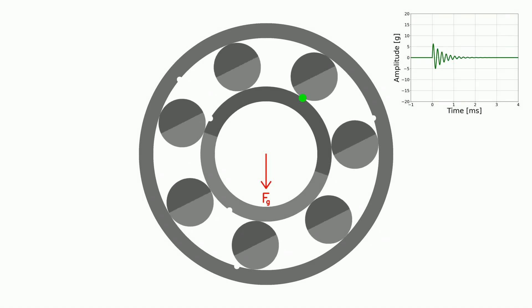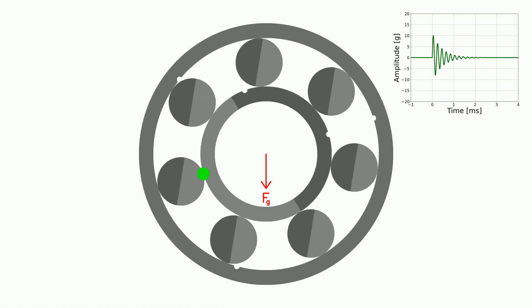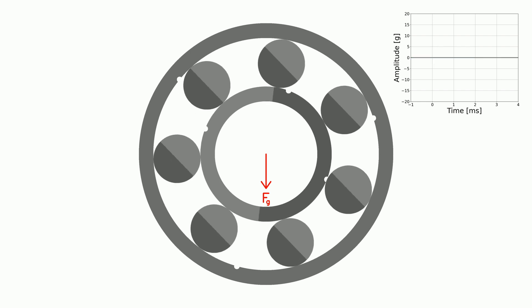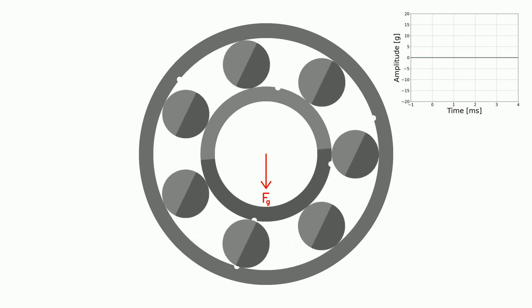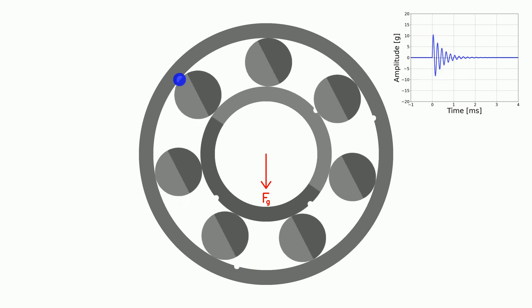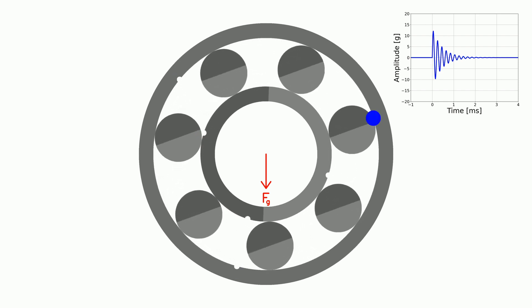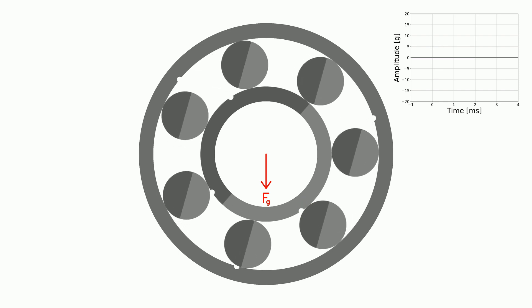There is another influence which may modulate the amplitude of shocks. Weight. Because of gravity, the weight of the horizontal shaft acts with a downward force Fg. It puts more pressure on the bearing balls under it than above. Shocks produced there are stronger.